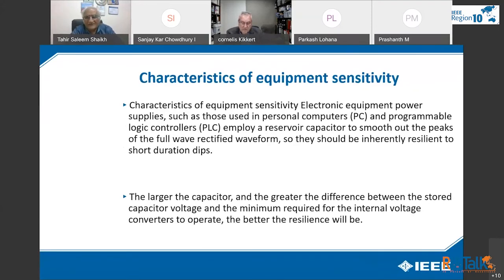Equipment sensitivity. Characteristic of equipment sensitivity: electronic equipment power supplies, such as those used in personal computers and programmable logic controllers, PLCs, employ a reservoir capacitor to smooth out the peaks of the full wave rectified waveform. So they should be inherently resilient to short duration dips. The larger the capacitor, the greater the difference between the stored capacitor voltage and the minimum required for the internal voltage converters to operate, and the better the resilience will be.